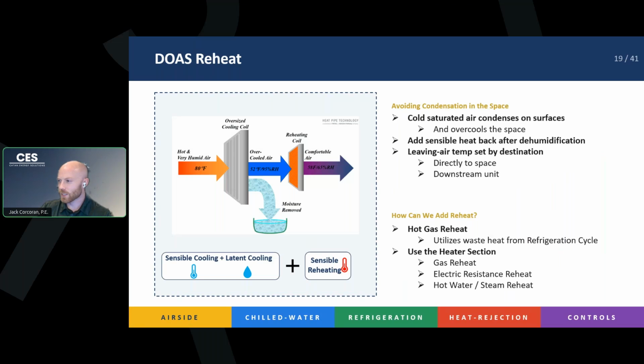And we talked last week in the rooftop units, right? You can have a reheat coil. So if you need to get rid of the humidity and there's a lot of it, let's wring it out, get that coil temperature super, super cold, and then you can reheat it back up sensibly. So that reheat coil is downstream of your cooling coil, and all it does is combine. You see underneath the image your sensible cooling, your latent cooling, and then you have sensible reheating. That reheat will drive that air temperature to any temperature you really need without adding in humidity. You're going to maintain the same number of grains per pound on our psych chart.